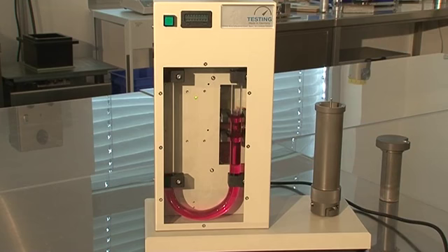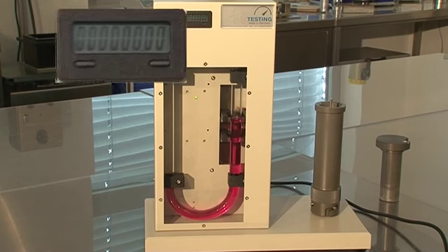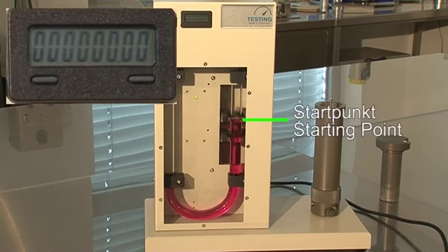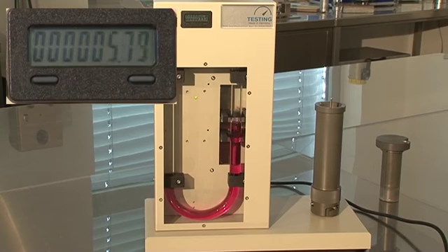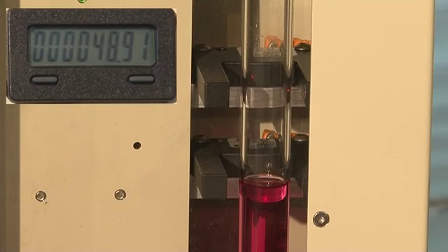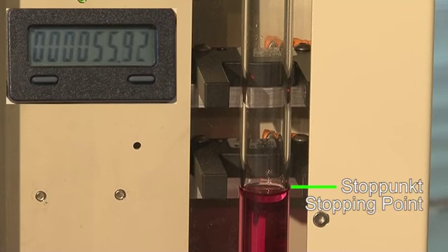The pump extracts oil until it reaches the upper suction point. As soon as the fluid meniscus reaches the upper photocell of the measuring section, the starting point, the measuring process begins and the dial gauge starts to run. When the liquid passes the lower photocell of the measuring section, the measuring process stops. The lead time is indicated on the counter.